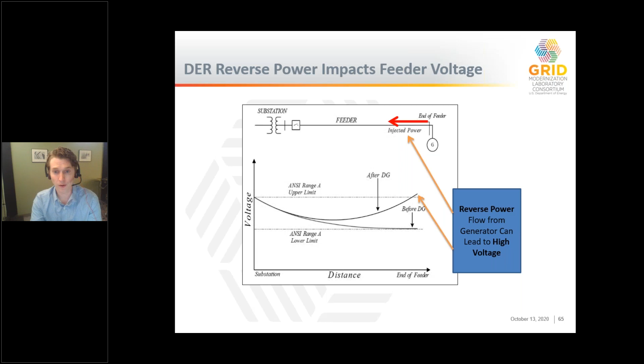Next slide, please. When we add DER onto the feeder, there can be reverse power flow, which can elevate the voltage in the area where the DER is producing power. There are really two ways to reduce voltage from the DER perspective, setting aside other types of mitigations.